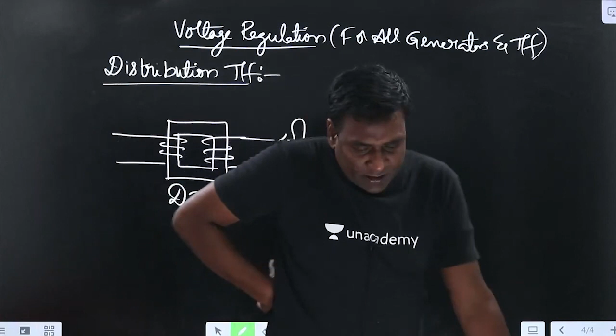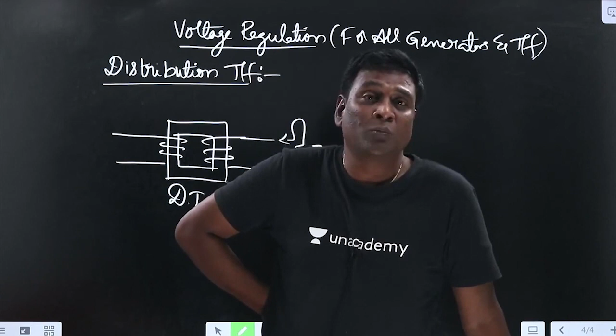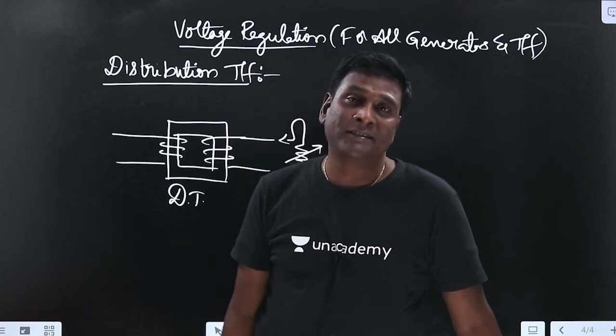Now for a distribution transformer, if you see voltage regulation, people say maybe voltage variation from no load to full load, but in that way no load to full load should not be defined for a distribution transformer. Why? Because my distribution transformer output is going to be variable. My distribution transformer can work at half load, it may work at full load. It may operate at 0.8 power factor lag, or it may operate at 0.5 lag also, because the loading conditions of the distribution transformer will be decided by the load.